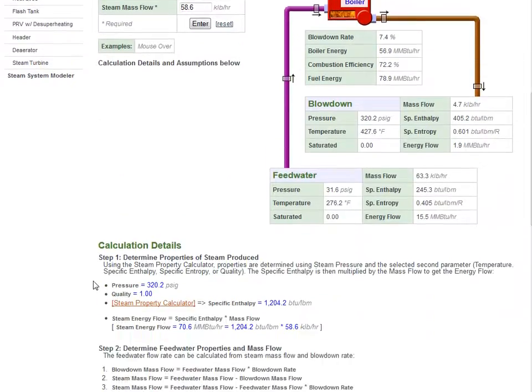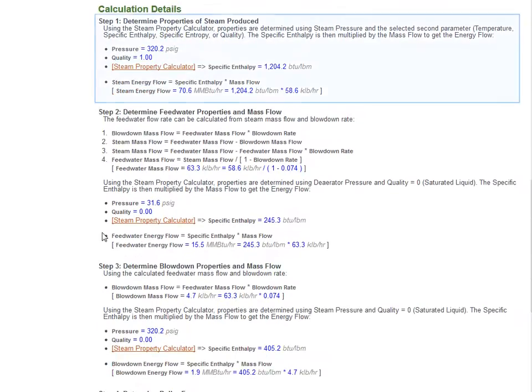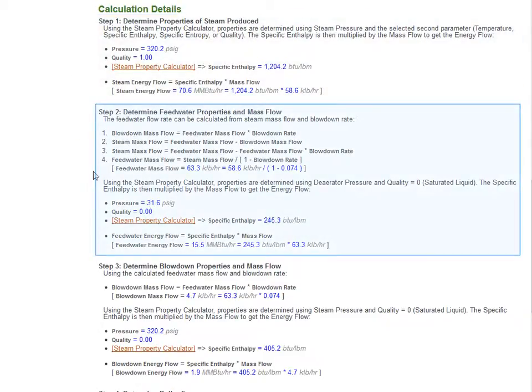The calculation begins by determining the properties of the generated steam. The mass flow of the feed water is then calculated using the blow down rate and steam mass flow. The properties of the feed water are set to those of a saturated liquid at deaerator pressure.